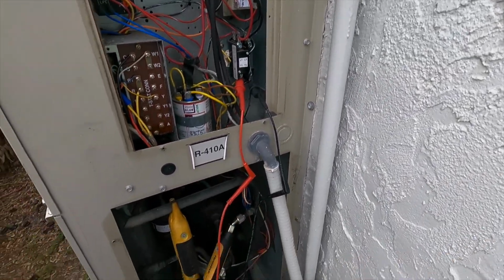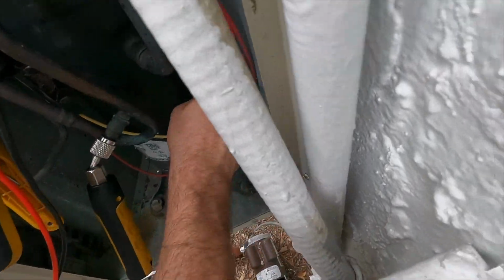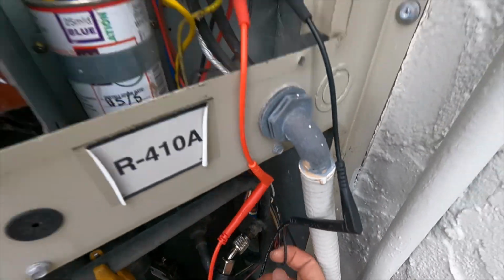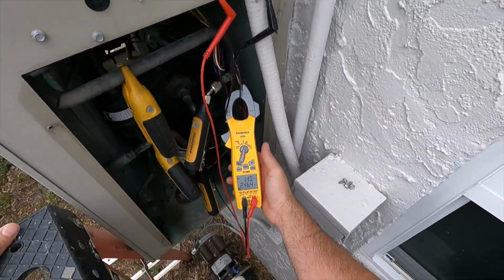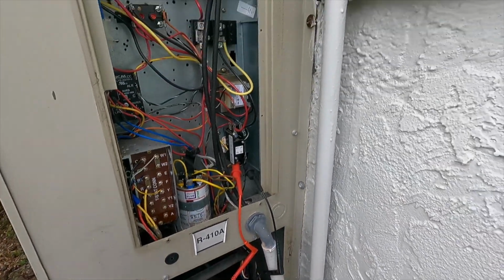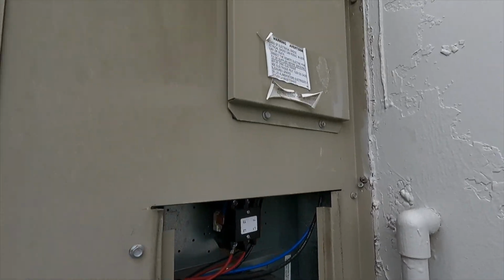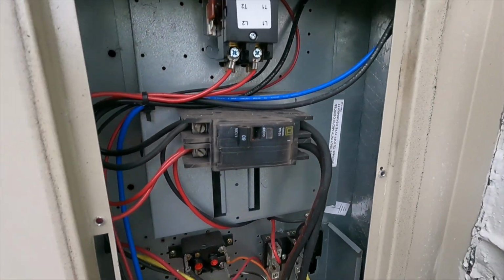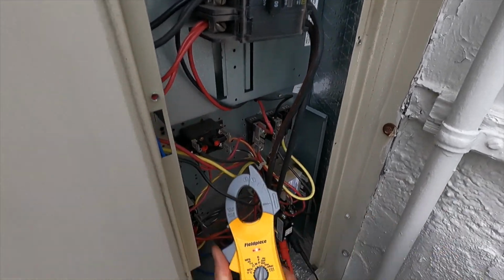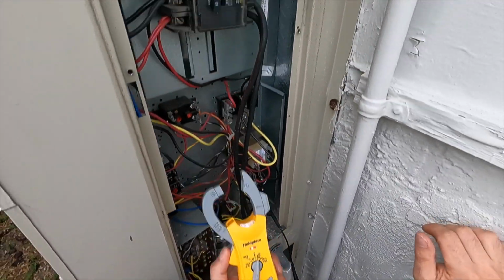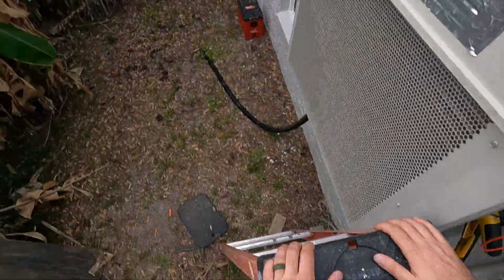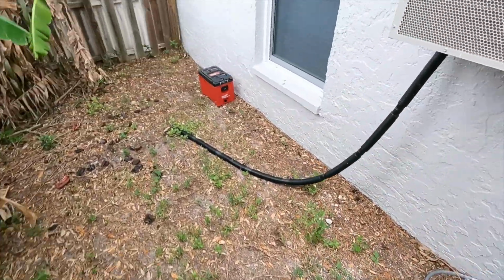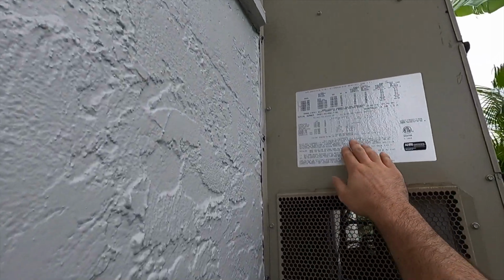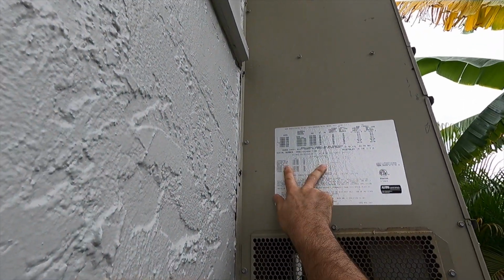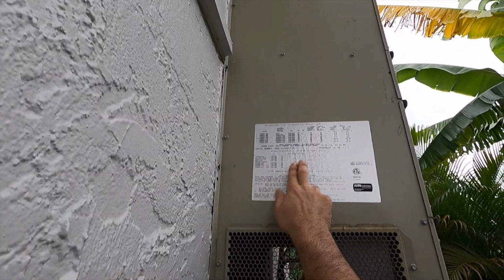So we'll go ahead and take a look at our fan motor, which should be it right there. 1.4. All right, if I had to take a wild guess here, go ahead and look at our blower. 1.7. We got 1.4 on the fan, 1.7 on the blower. 1.5 on our outdoor motor. So we're close. Indoor motor, 2.1, 1.7. So we're doing all right on that.